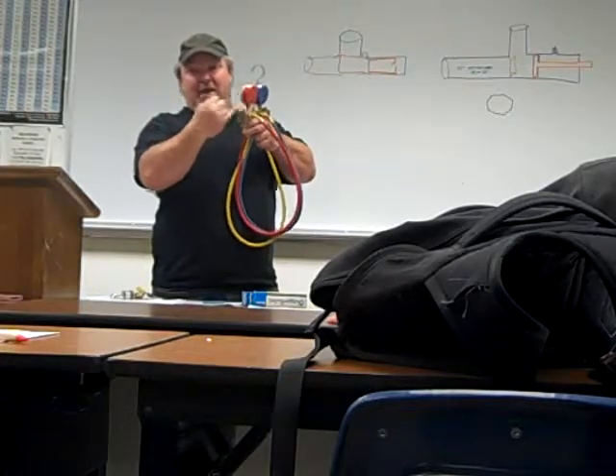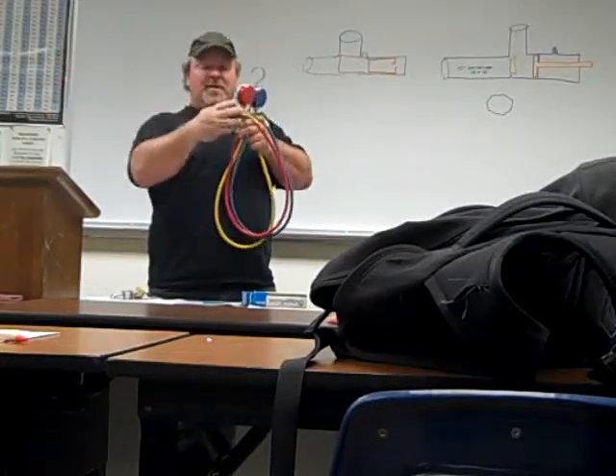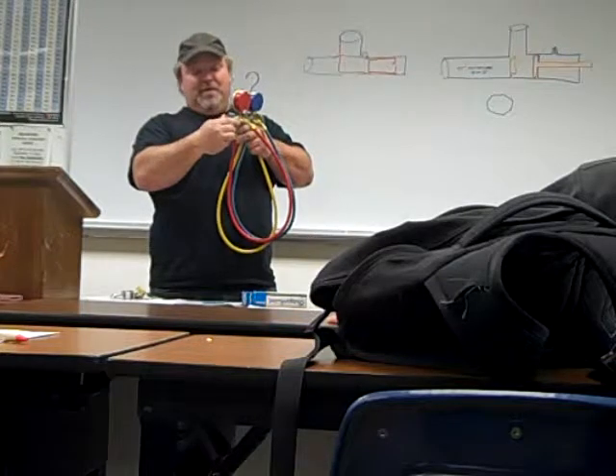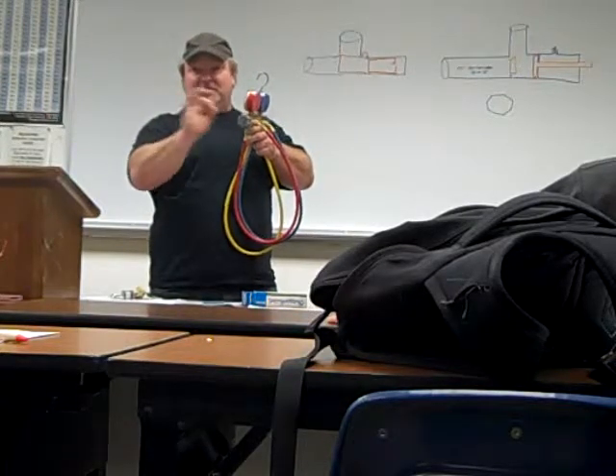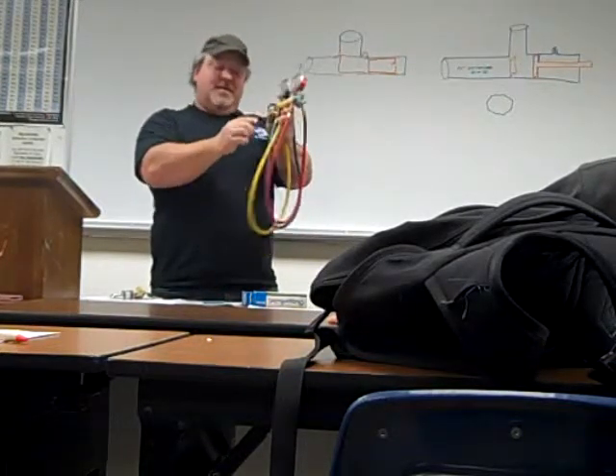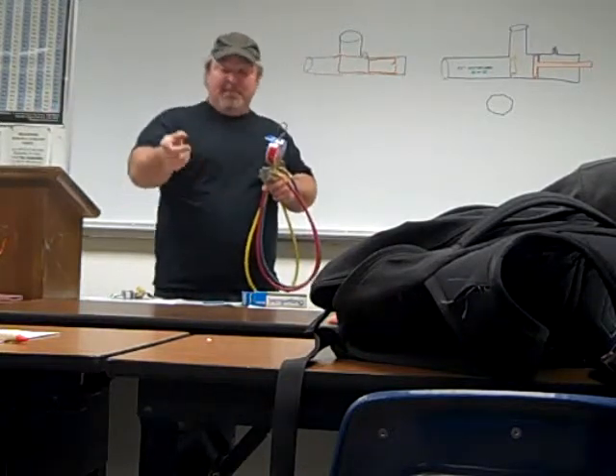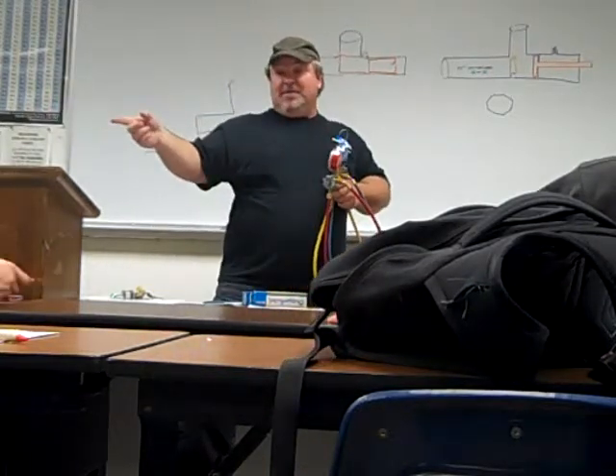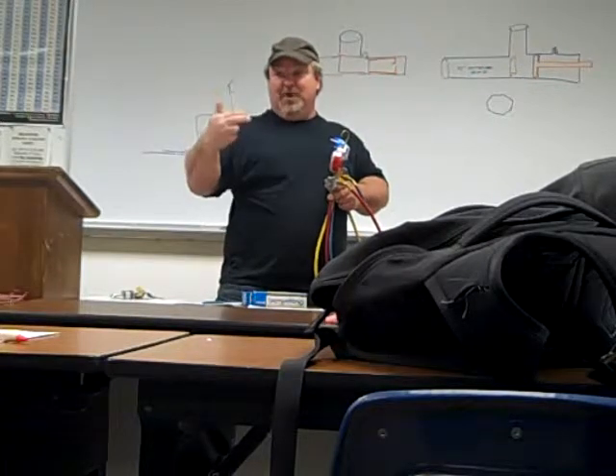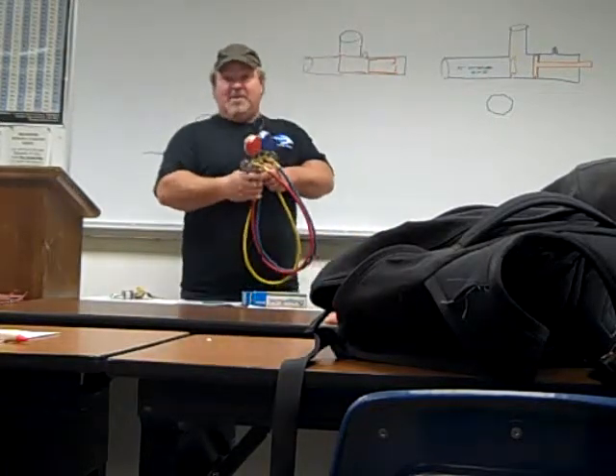If you open it wide open, you're dumping liquid right through it. But you just barely crack it open, just enough to get a metering system in here. And you can use this as a metering device. That's basically what that is. It's just a metering device in there. It's high pressure to low pressure, and it lets it vaporize off.